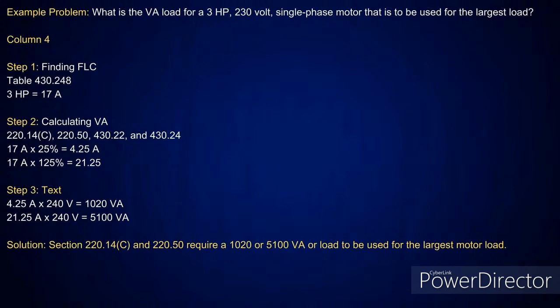Now, if I look at this, I've got a 3 horsepower, 230 volt single phase motor. Since it's single phase, I'm going to be looking at table 430.248. And if I pick up my 3 horsepower for 230 volts, it's going to tell you it's good at 17 amps. You can look at all these sections, they tie in here. For a single motor, you're looking at 430.22. If I have multiple motors, I'm looking at 430.24 and selecting the largest one. Basically, I'm going to take every one of those motors at 100%, but the largest one, I have to add an additional 25% on that. So in this case, the 17 amp was the largest motor. I'm going to take it at 25%, which gives me 4.25 amps, and I'm going to add that on there.